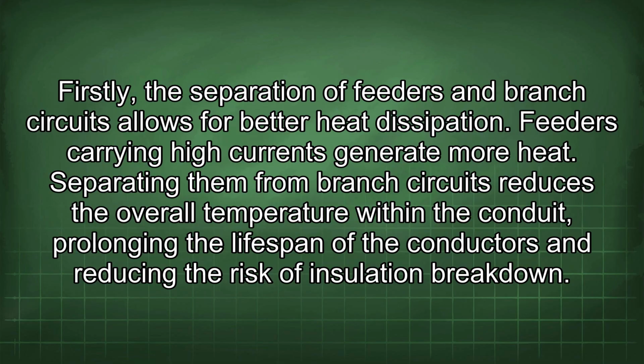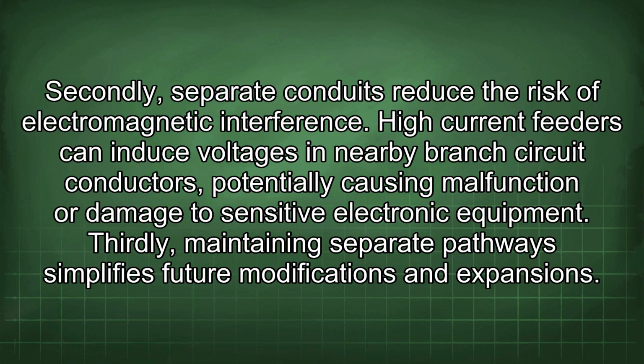Firstly, the separation of feeders and branch circuits allows for better heat dissipation. Feeders carrying high currents generate more heat. Separating them from branch circuits reduces the overall temperature within the conduit, prolonging the lifespan of the conductors and reducing the risk of insulation breakdown. Secondly, separate conduits reduce the risk of electromagnetic interference. High current feeders can induce voltages in nearby branch circuit conductors, potentially causing malfunction or damage to sensitive electronic equipment.